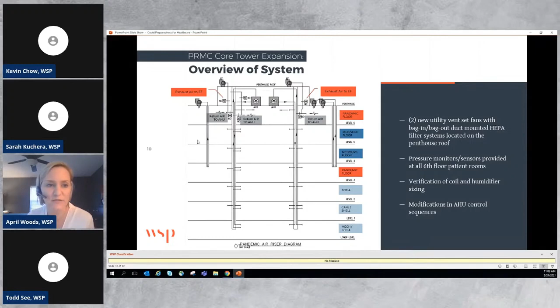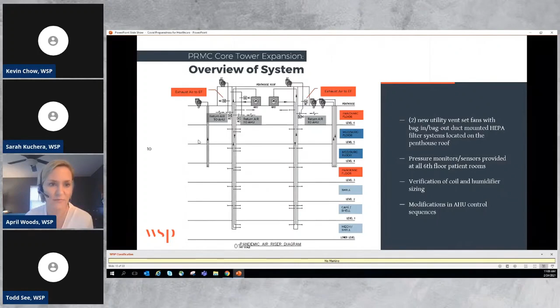With that as well, we had pressure monitors provided in all 6th floor patient rooms, so there could be verification that we were meeting negative pressure prior to anybody entering those spaces. And of course, as we increased the exhaust quantity by quite a bit on these floors, we also verified that the coil and humidifier was sized adequately, both for cooling and heating system. And of course, there were some modifications made to the control sequences for the automatic control of those motorized dampers, and also allows them to do some fan testing sequences when they're not in pandemic operation.